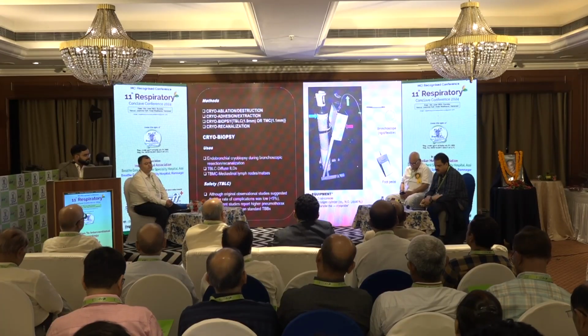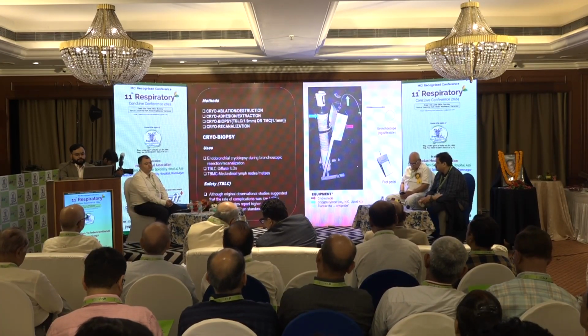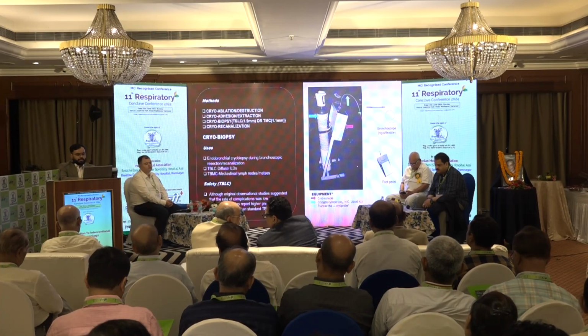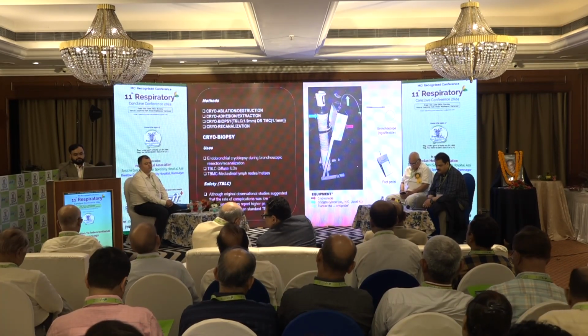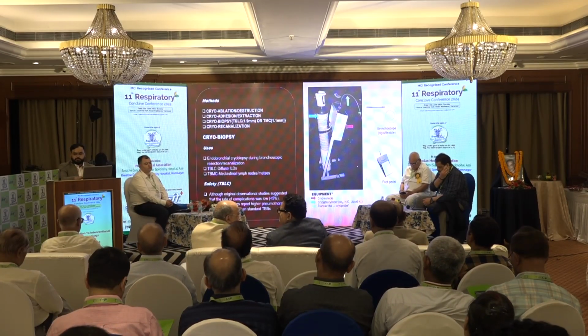If we can see this console, it has a cryogen cylinder which contains pressurized carbon dioxide, N2O or liquid nitrogen. The cryogen cylinder then delivers this gas into the cryo console, and then the cryo console ultimately transfers it to the cryo probe, with which we are going to get a biopsy. And there's a foot pedal which we can use to deliver the gas.